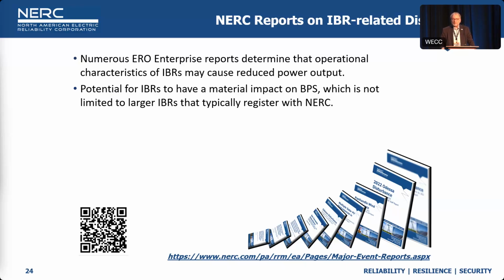We had over 25 substations that were affected and over 60 different owners of data systems that were affected by that. None of those were initiated or load tripped because of a utility initiated situation, but it was all behind the meter, internally to them. Their protection system saw that fault and immediately came offline. If that's the case, and we begin to see larger and larger concentrations of data centers near generation or near other areas, we're going to need to make sure that they have the ability to ride through those scenarios similar to what we're talking about for inverter-based resources.